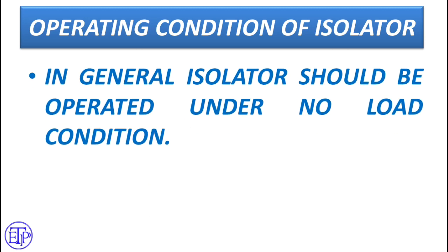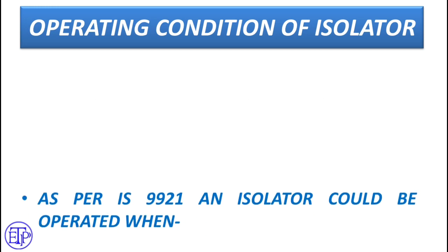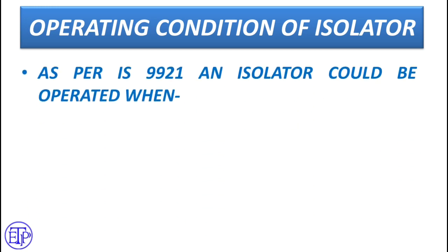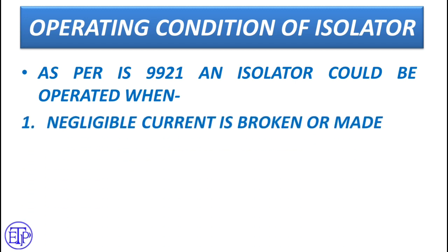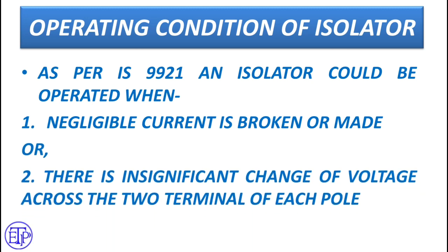First we will see what is the basic operating condition of the isolator. In general, an isolator should be operated under no-load condition. This is the theory — as per theory, an isolator should only be operated under no-load condition. But there is a big question mark. As per IS9921, an isolator could be operated when negligible current is broken or made, or there is an insignificant change of voltage across the two terminals of each pole. Watch these two points very carefully — they basically support the philosophy of no-load operation.